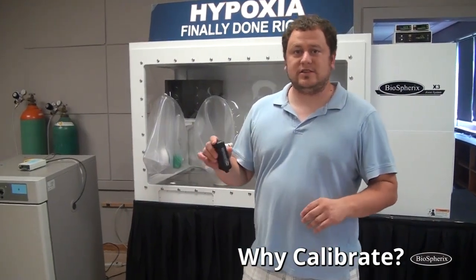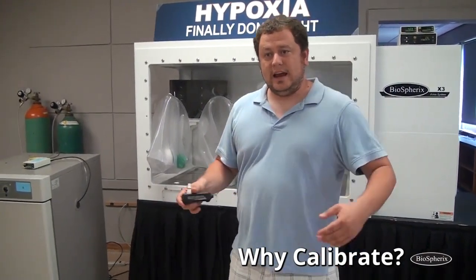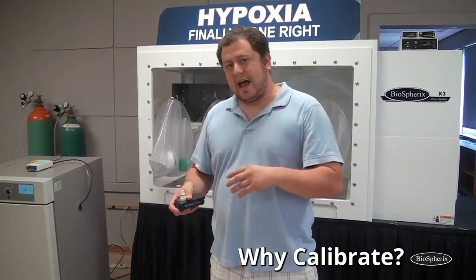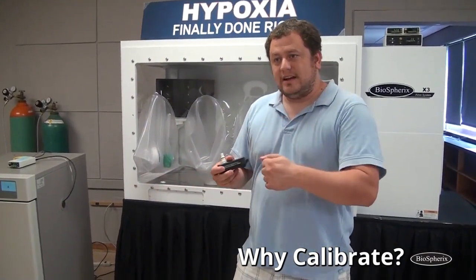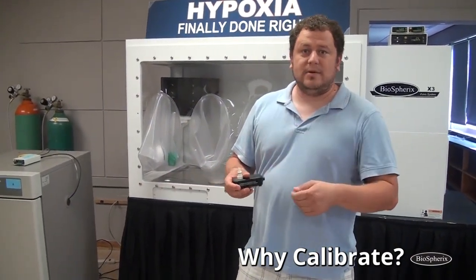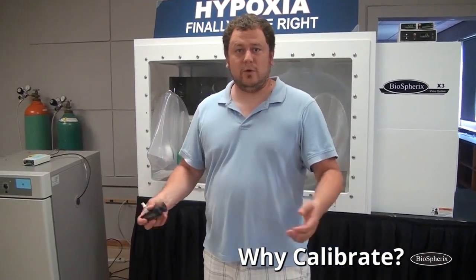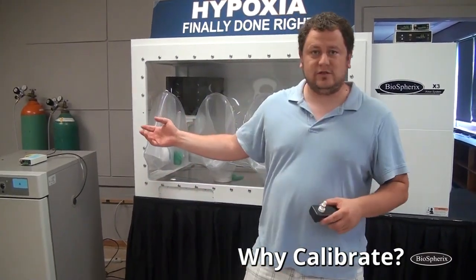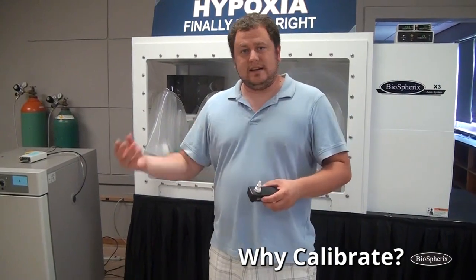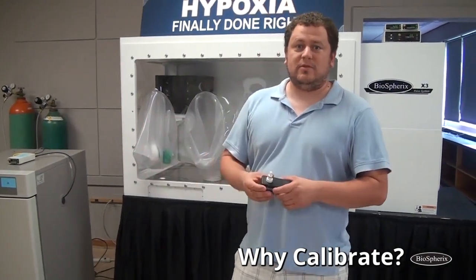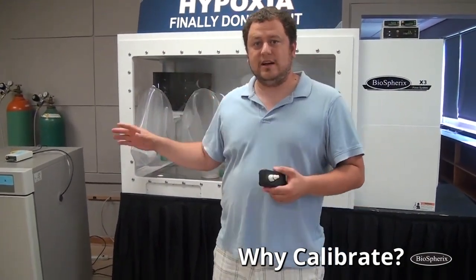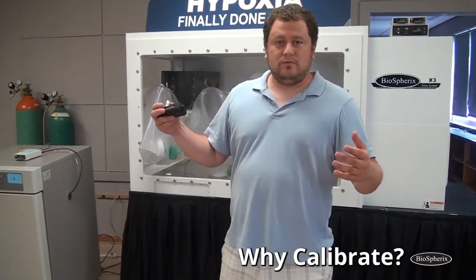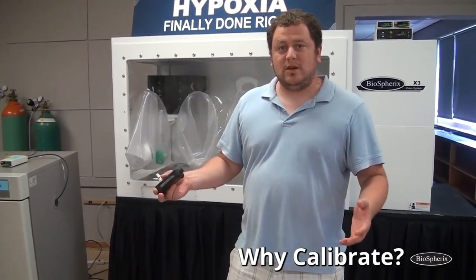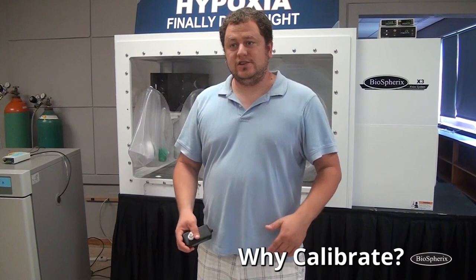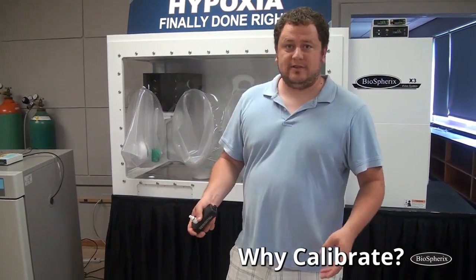The sensor is an electrochemical sensor, and when it is exposed to oxygen, the chemical inside of there is consumed, it's used up, and it gives off a millivolt reading, and that's what the controller is actually reading. But it eats itself, it eats that chemical up over time, and that causes the sensor to drift. And basically about once a month is what we recommend, is you want to account for that drift.